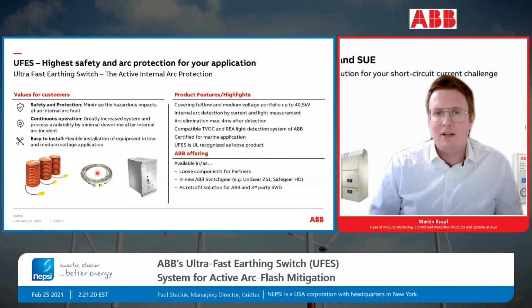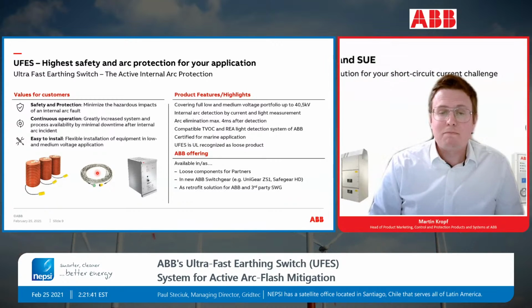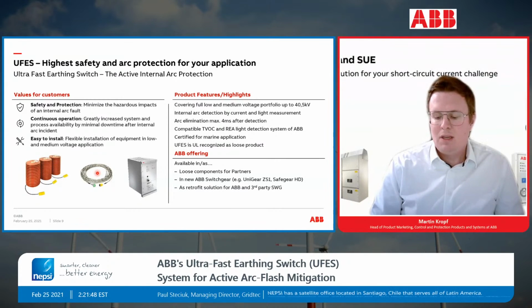As I said, we cover full medium and low voltage, and we are compatible. On detection, I went briefly through it - we work with very well proven ABB technology like TVOC for low voltage, or our REA protection relays for medium voltage, which are very optimized for light detection. We are, for instance, marine certified, and as well as UL recognized as a loose product.